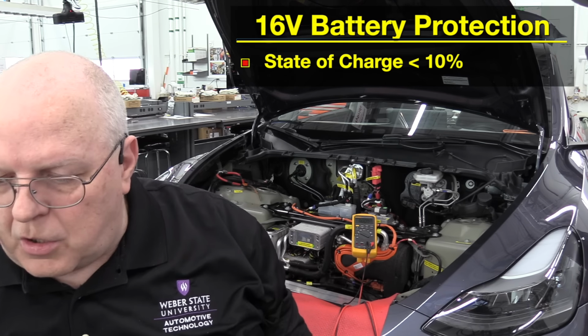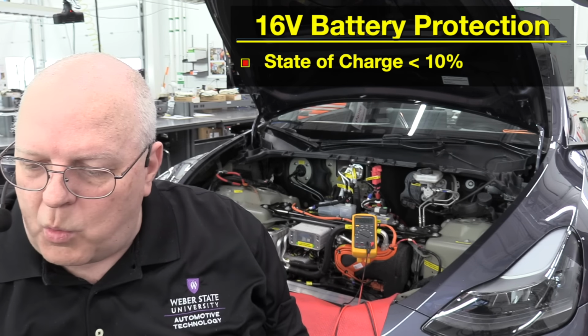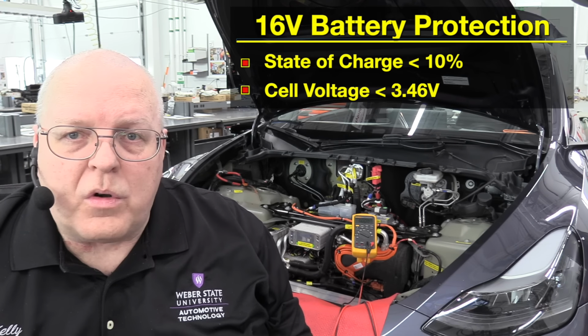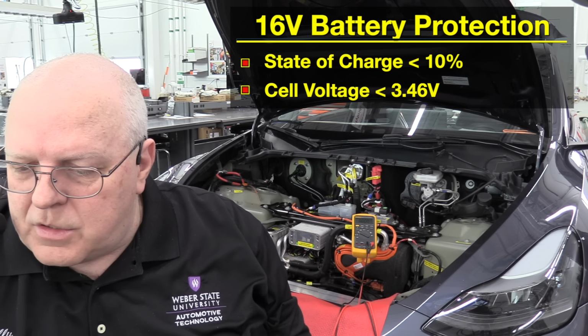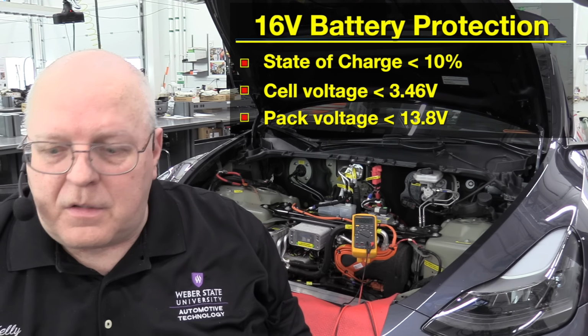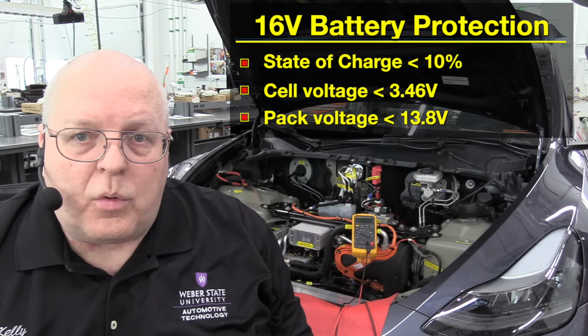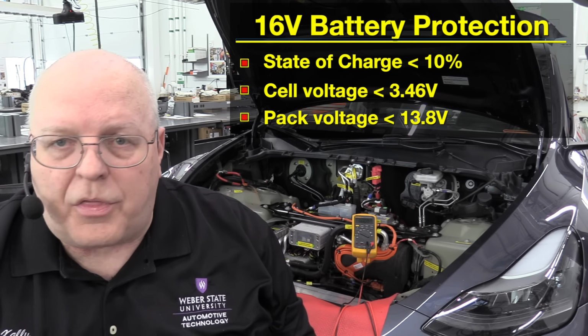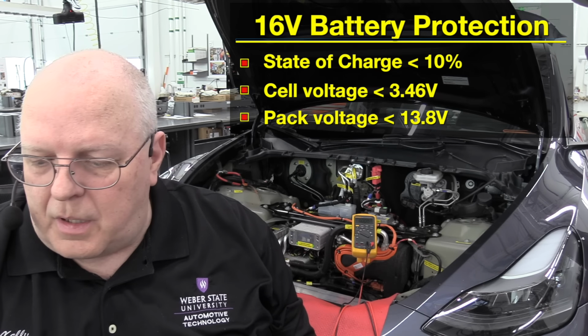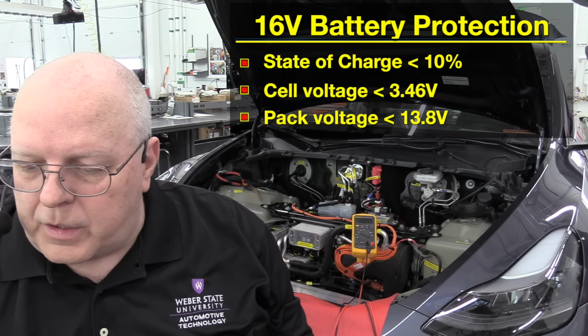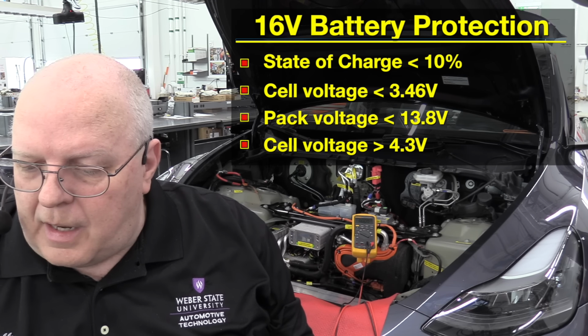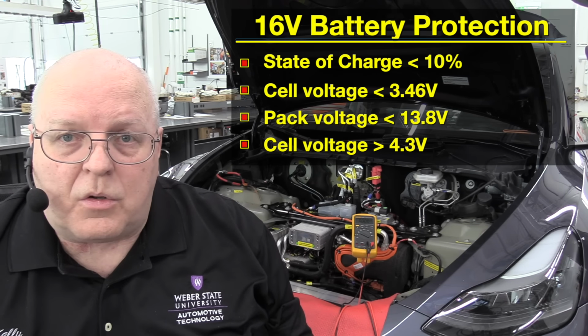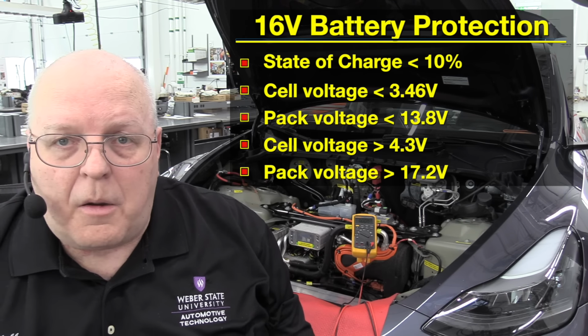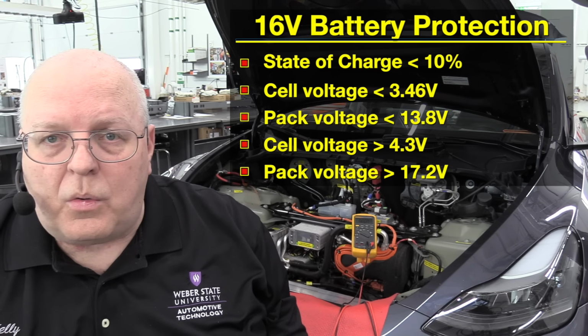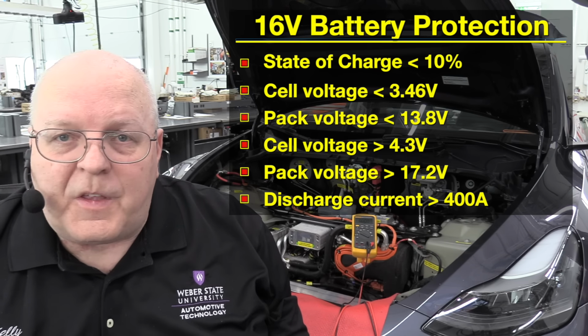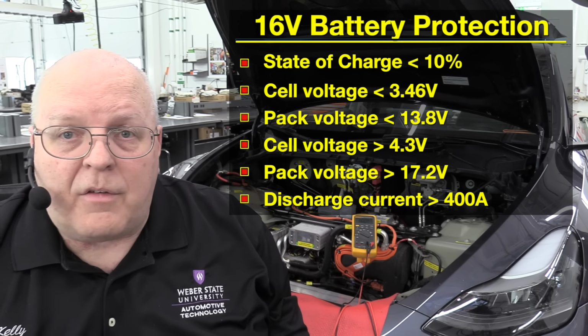So that's the state of charge condition, but there's more. Any of the 4 cells that have a voltage lower than 3.46, or if the entire 12 or 16 volt battery pack has a voltage less than 13.8 volts, it'll also go into protection, and that's for low voltage. For high voltage, any of the 4 cells that goes above 4.3 volts, or the entire battery pack voltage goes above 17.2, the MOSFET can open. It'll also open if the discharge current is greater than 400 amps.